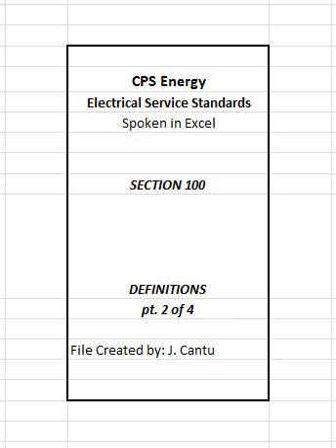A service-rated fuse pad furnished and installed by CPS Energy on customers' premises that will be used by CPS Energy to disconnect the customer's secondary service conductors from the downtown network system. The service-rated fuse pad shall be property of CPS Energy and remain locked and sealed by CPS Energy personnel at all times. Ground.